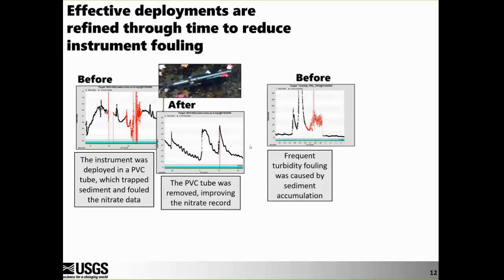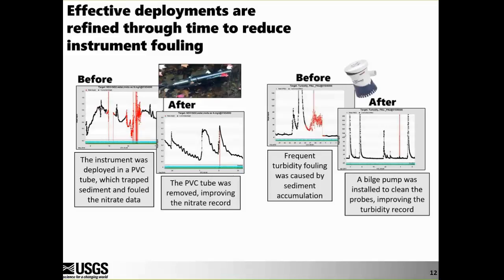Another site refinement example: a turbidity record shows that after large storm events, fine sediment deposits on instruments as the stream recedes to base flow, causing fouled turbidity records at the end of storm events. To address this, we installed bilge pumps near the instrumentation that pump ambient water across the face of the probe to clean off fine sediment. After a bilge pump was installed, we see a much cleaner turbidity record through storms.